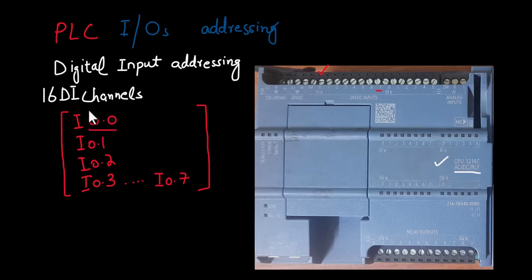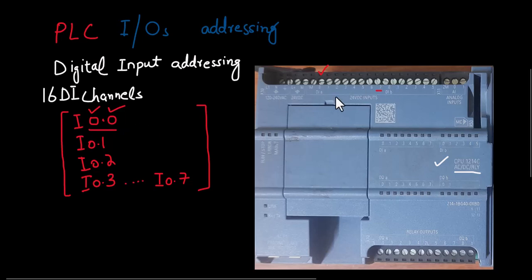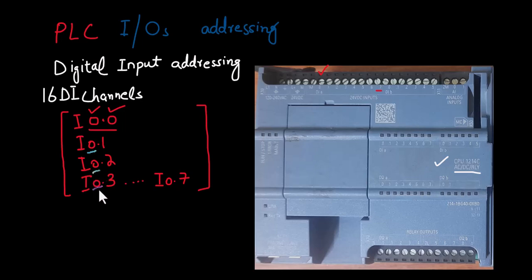As we have discussed in the PLC data types, a byte is one PLC data type and it has eight bits. So the number that is towards the left of the decimal point represents the byte number, while the number that is on the right side of the decimal point represents the bit number. So the first eight digital input channels will lie in the first byte, because a byte has eight bits — we will number it as byte 0. The input channel bits of each byte will be numbered from 0, 1, 2, 3, all the way to 7.